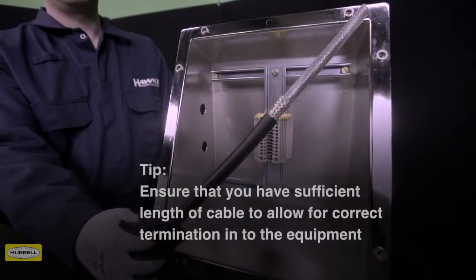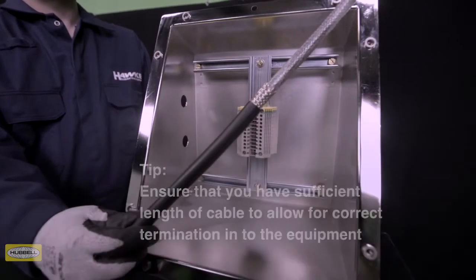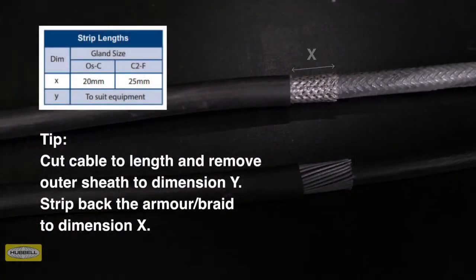Allow sufficient length of cable to suit the equipment the cable is being terminated into. Strip the outer sheath and cut the armor to enable connection of the conductors to the terminal. Remove a further 20 millimeters of armour for cable glands OS to C size, and 25 millimeters for C2 to F size.